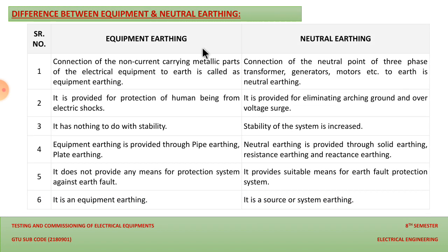And what actually is the difference between equipment earthing and neutral earthing? Let us discuss with the table given below. This is equipment earthing, and this is neutral earthing. Equipment earthing is the connection of the non-current carrying metallic parts of the electrical equipment to the earth.